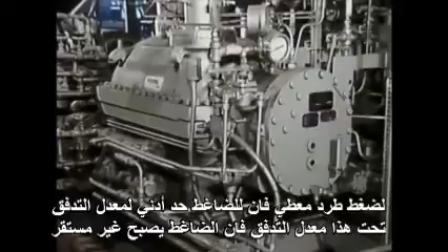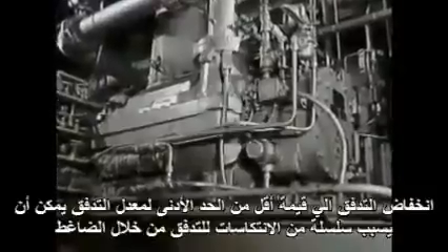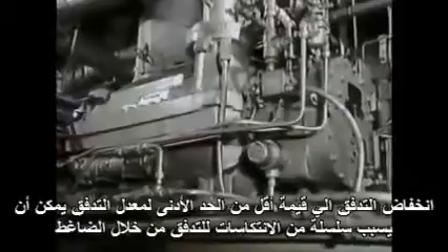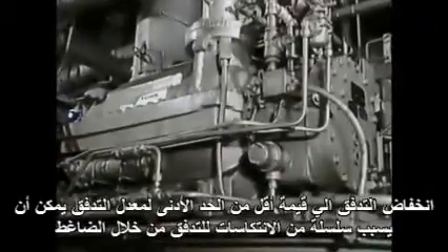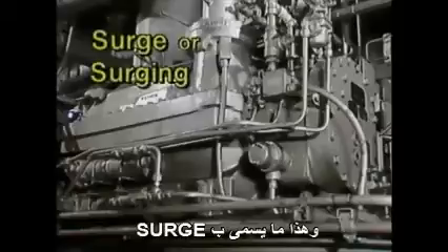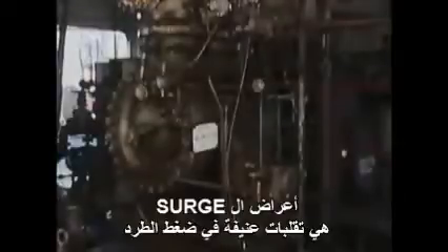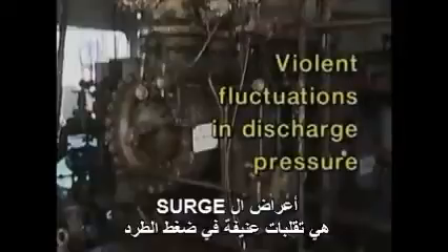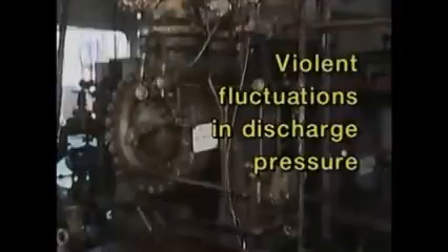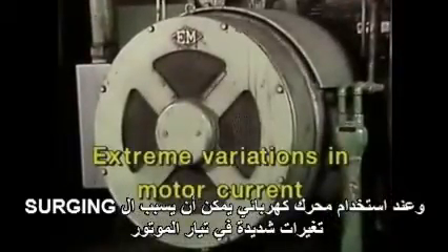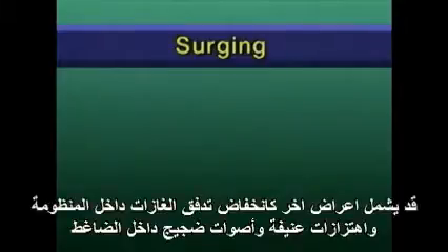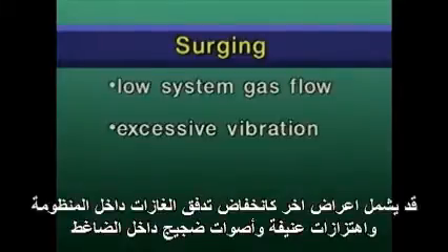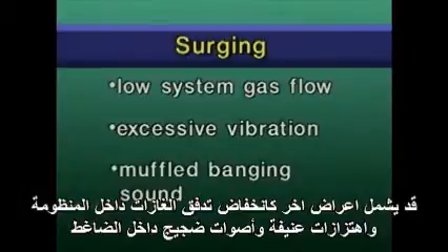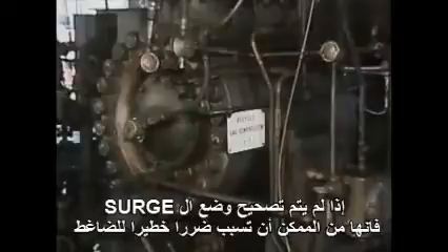Below this flow rate, the compressor becomes unstable. A decrease in flow below the minimum flow rate can cause a series of momentary reversals of flow through the compressor. This situation is called surge or surging. The symptoms of surging are unmistakable. Surging results in violent fluctuations in discharge pressure. And when an electric motor is used as a driver, surging can cause extreme variations in motor current. Other symptoms include low system gas flow, excessive vibration, and a muffled banging sound inside the compressor. If surging is not corrected, it can cause serious damage to the compressor.